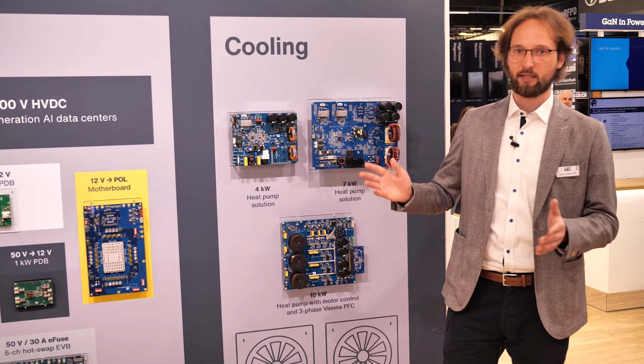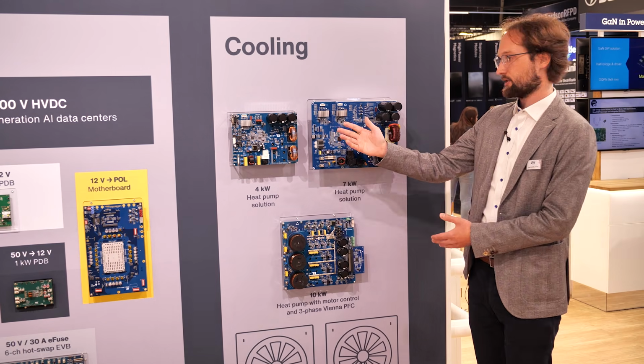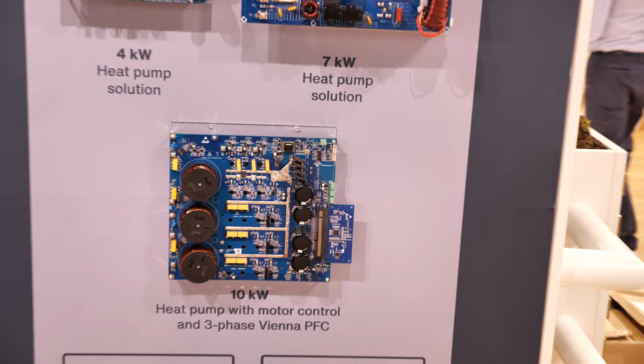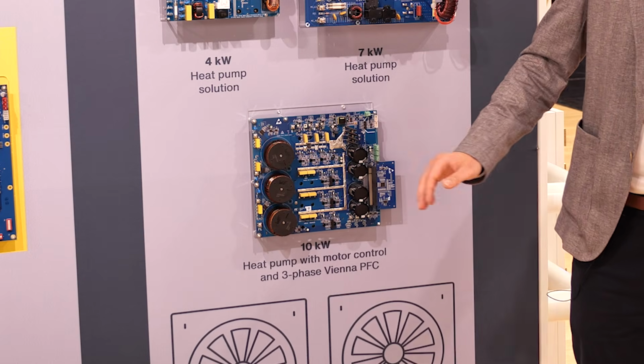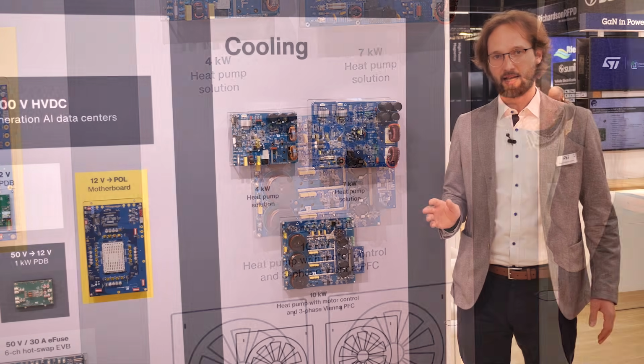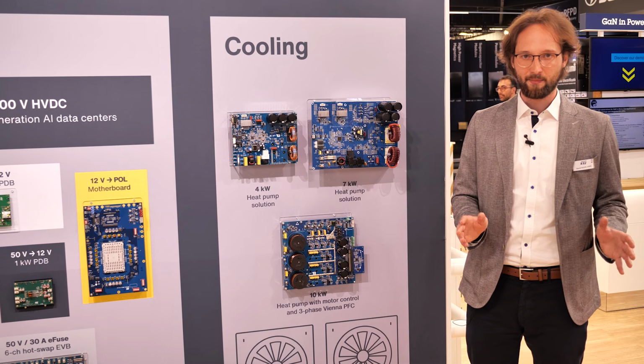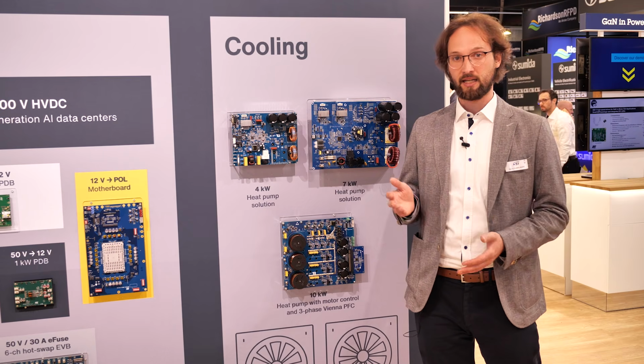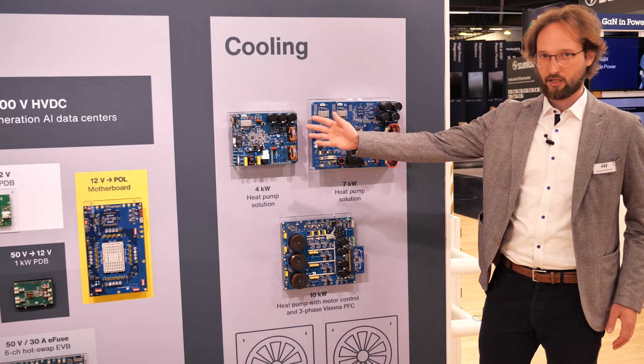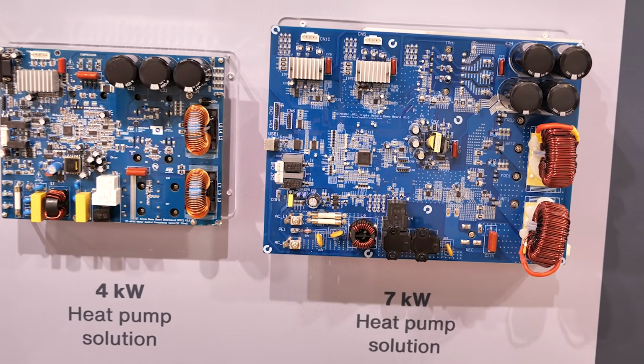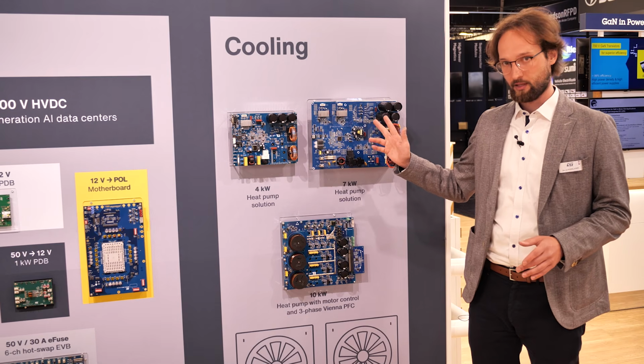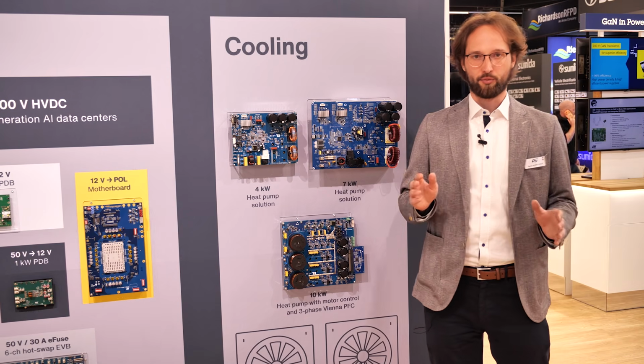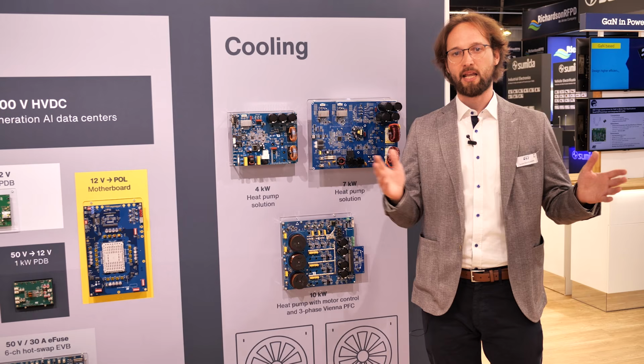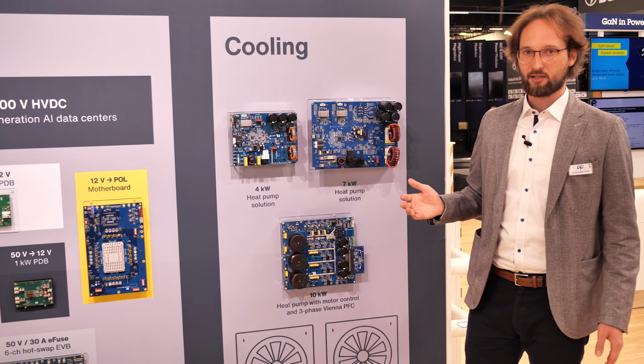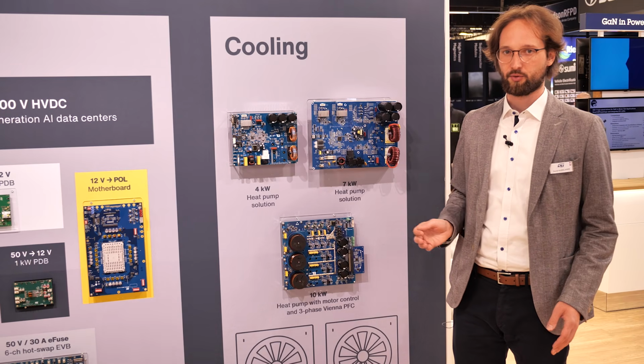And heat pumps need motor drives. The three solutions on this panel are 4 kilowatt, 7 kilowatt and 10 kilowatt heat pumps. The 10 kilowatt uses three-phase Vienna PFC and motor control based on the same ST silicon carbide MOSFETs we have seen in the power supplies. The 4 kilowatt and the 7 kilowatt boards implement interleaved PFC and dual or triple motor drive, accommodating both compressor and fan drives on the same board, which are handled by ST's compact and efficient intelligent power modules called SLIMs.